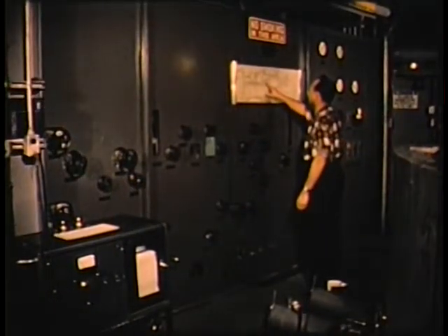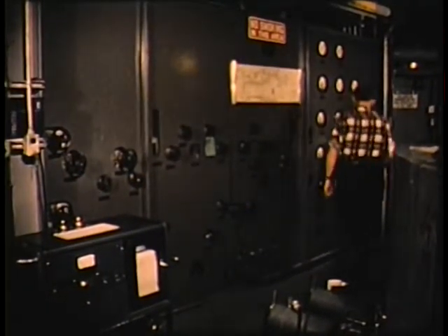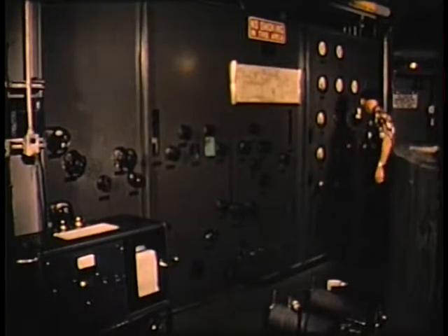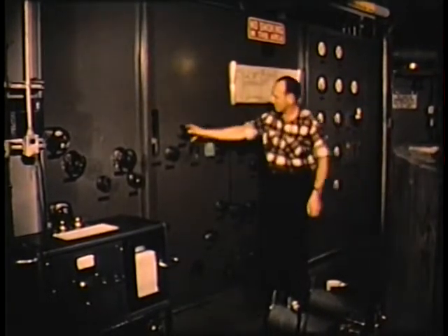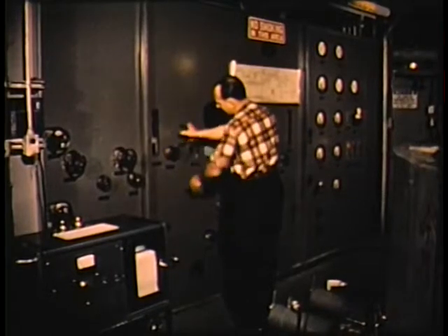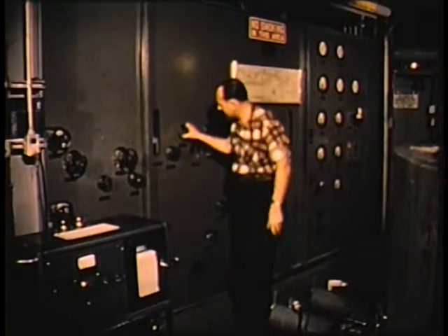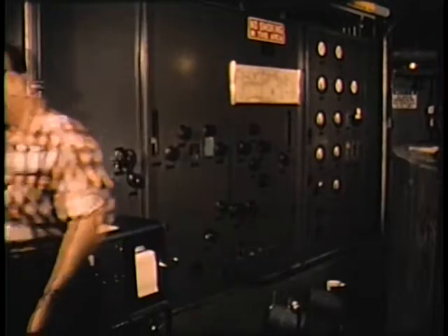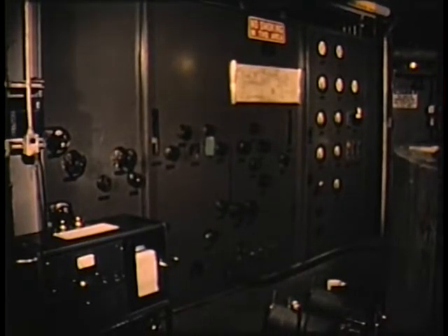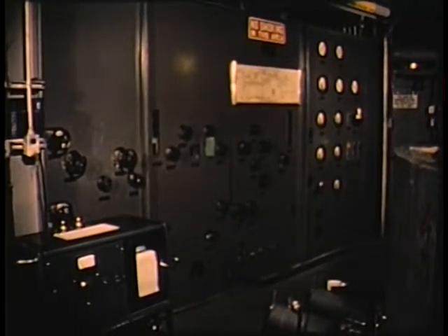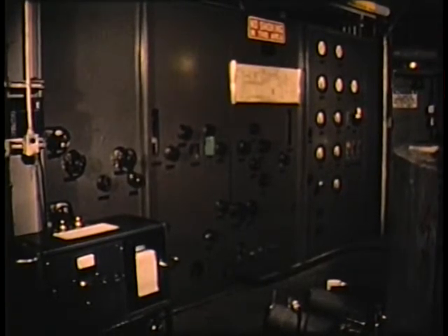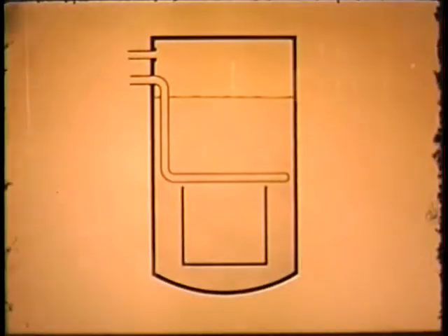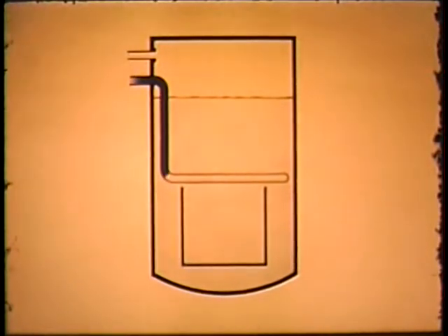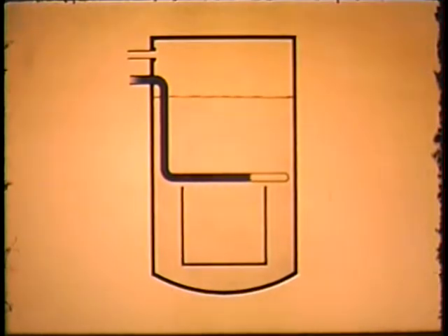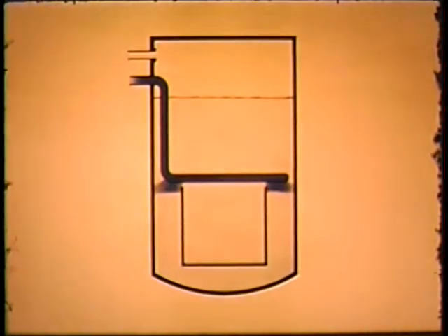Before the condensate enters the pressure vessel, it passes through the secondary circuit of the purification system heat exchanger. There, it cools water being pumped from the reactor for filtration and ion removal at a rate of approximately 3 gallons per minute. Such cooling is necessary because of the temperature limitations of effective ion exchange. The purified water mixes with the water used to cool it, and the mixture, now termed feed water, enters the pressure vessel through the lower feed water spray ring.